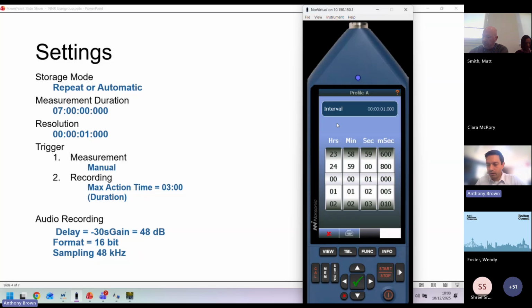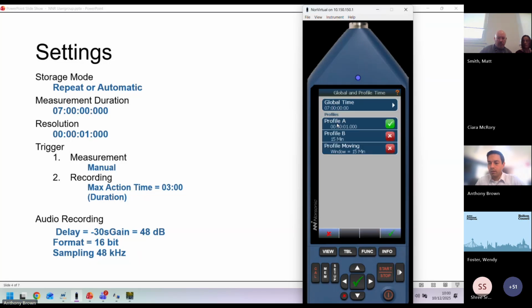If we press the tick on the screen, that's saved, and now I've got 1 second in profile A. You can ignore profile B and profile moving - some meters won't have this. But for those doing environmental measurements where you need a 15-minute value, maybe an hour, you can log this as an additional parameter.